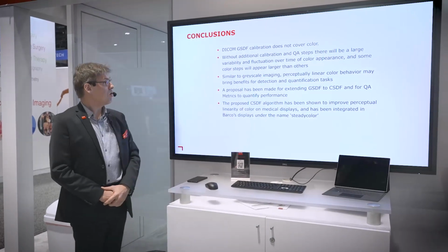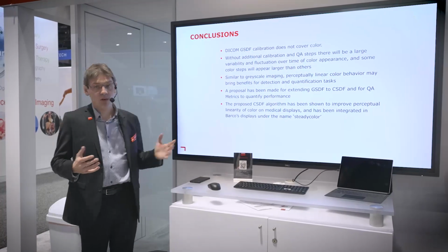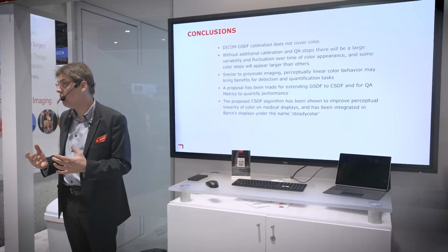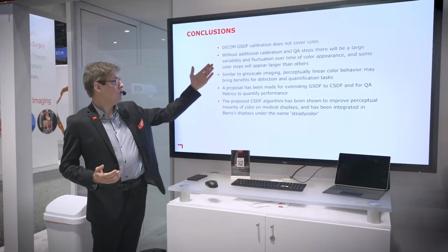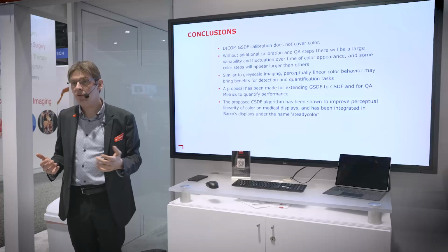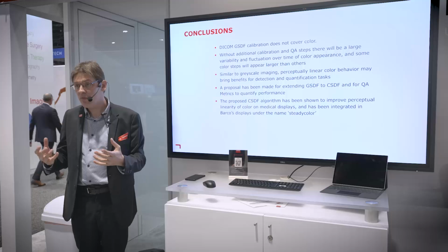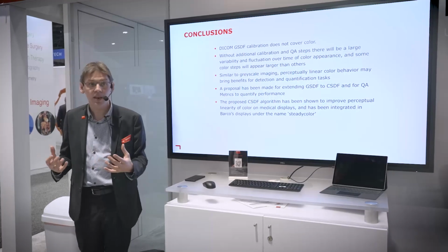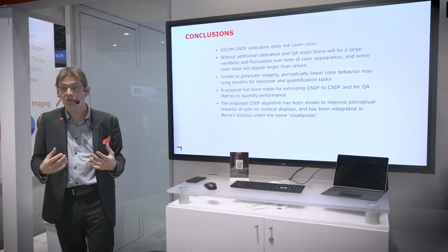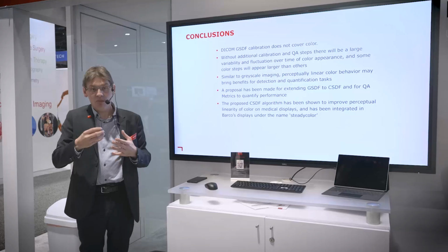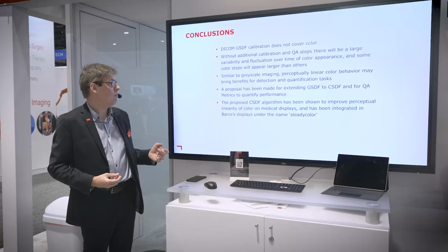Okay, concluding, so be aware, color is used a lot, you know that. DICOM GSDF calibration is not going to help you with calibrating color or having QA of color. So if you don't do anything, you'll be having issues with the color representation. You will not see all the colors. Some colors will be more easily visible than others, and certainly it's not going to be perceptually linear. So if you have color ramps or color scales, some differences will be very large, other ones will be hardly perceivable.